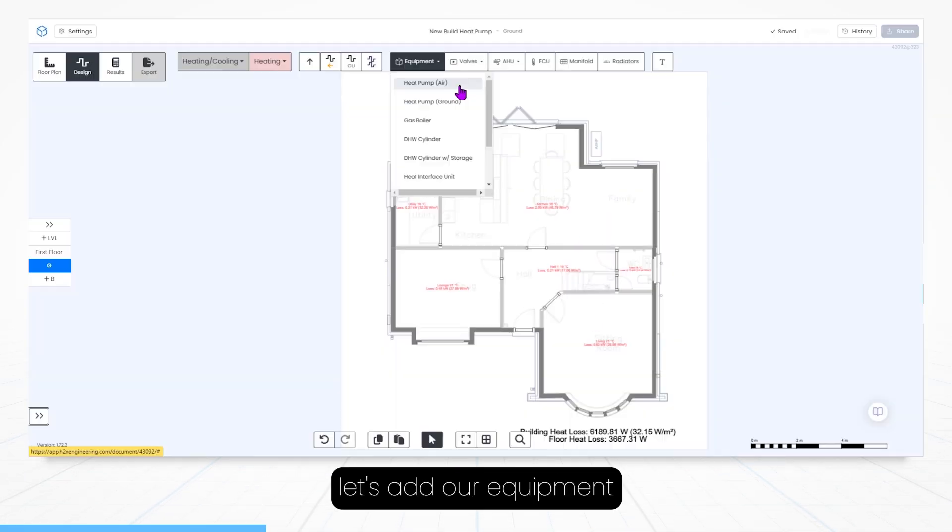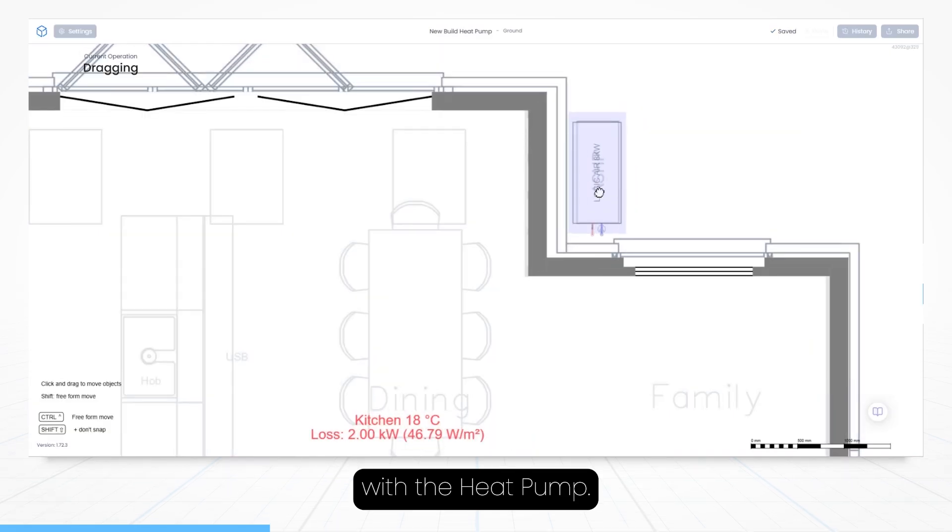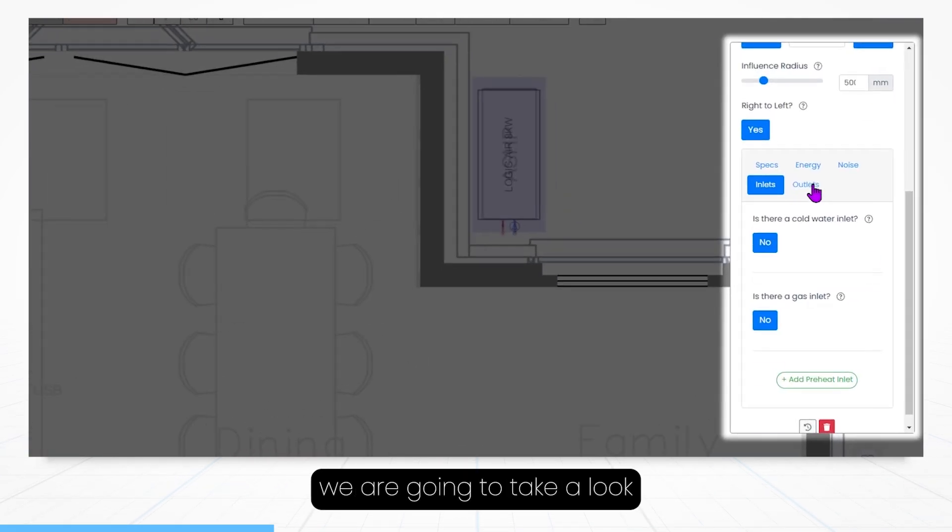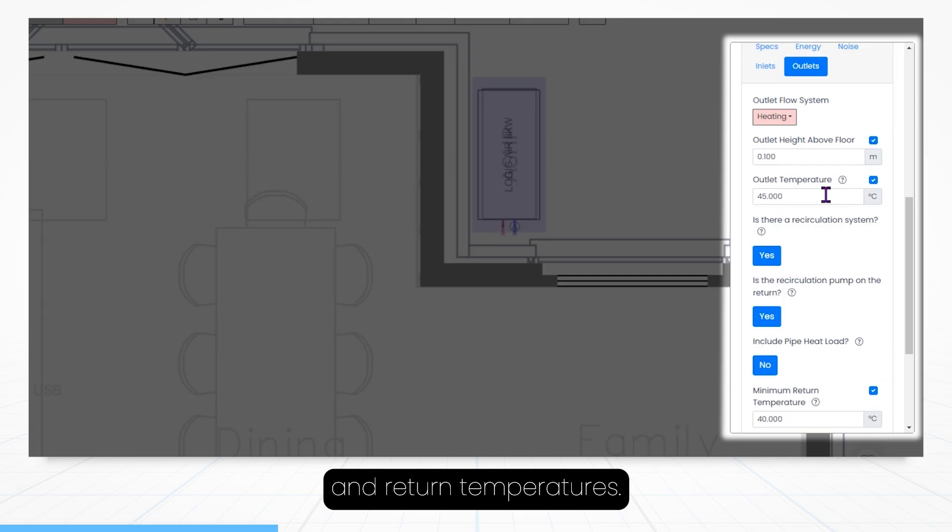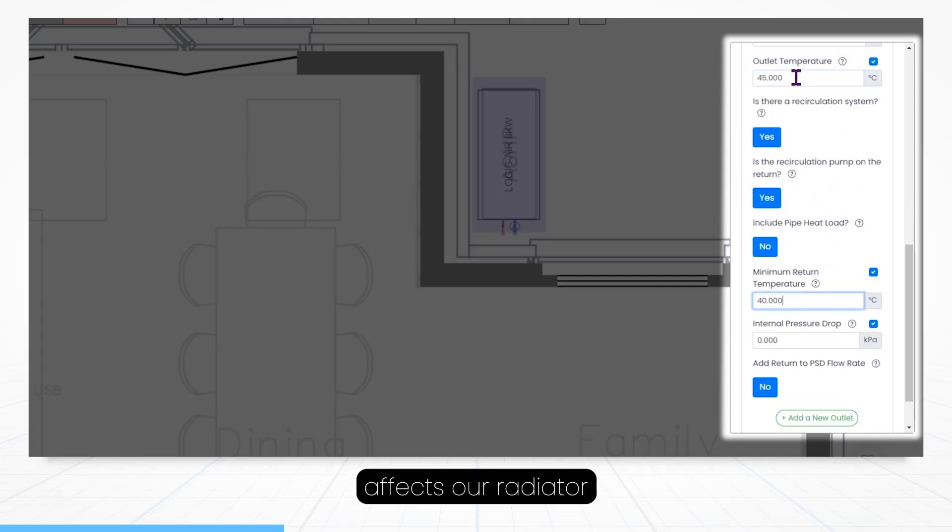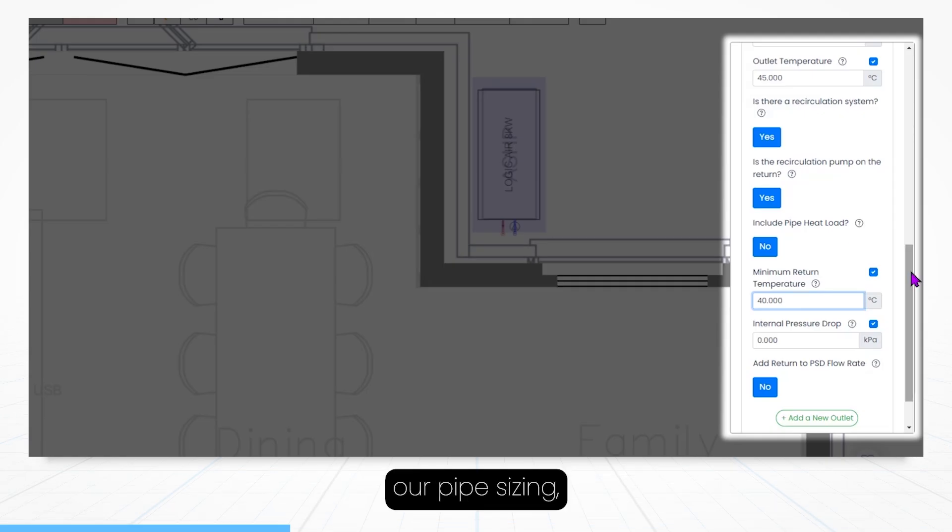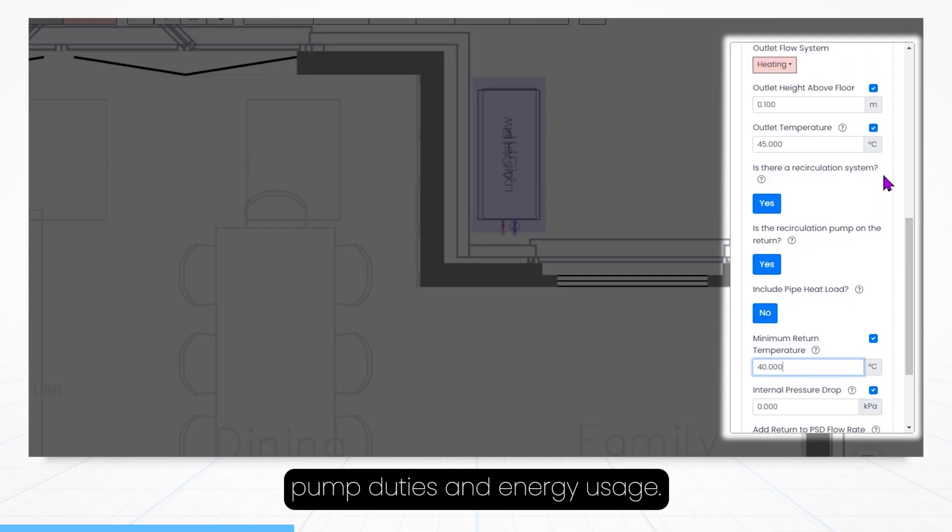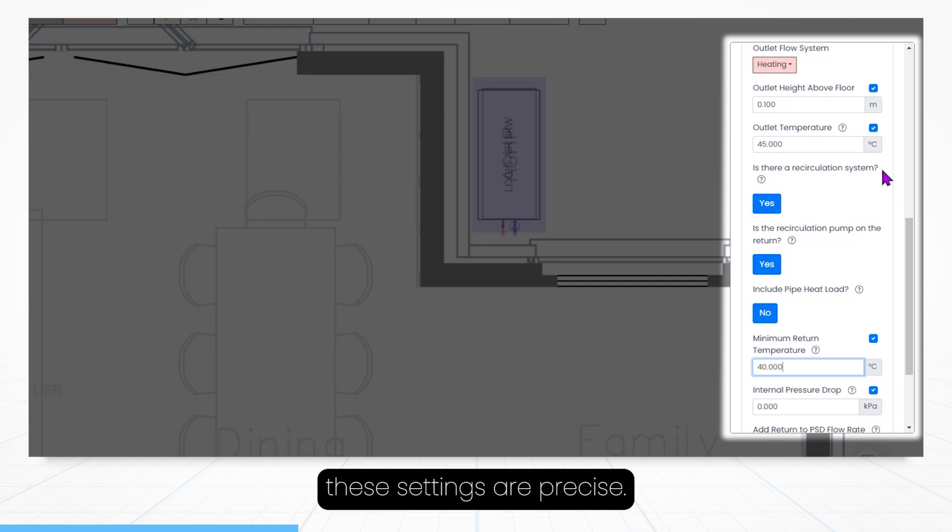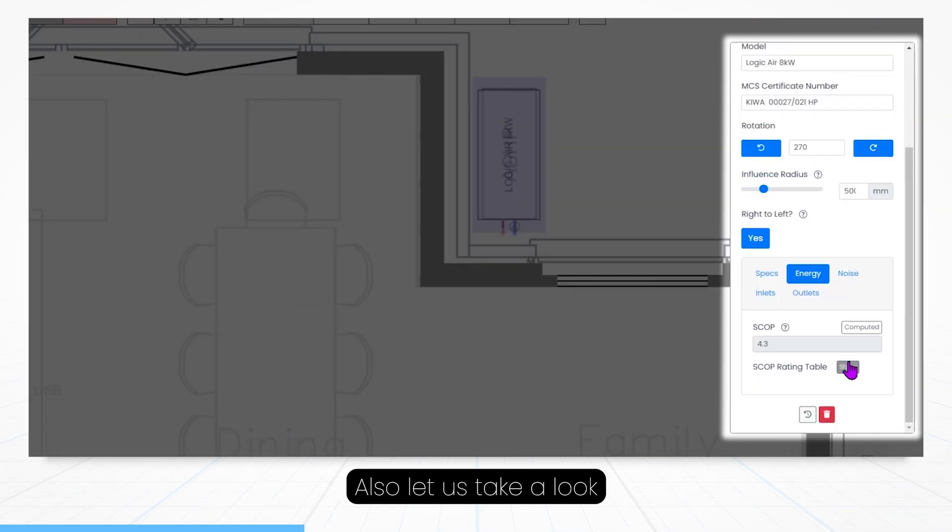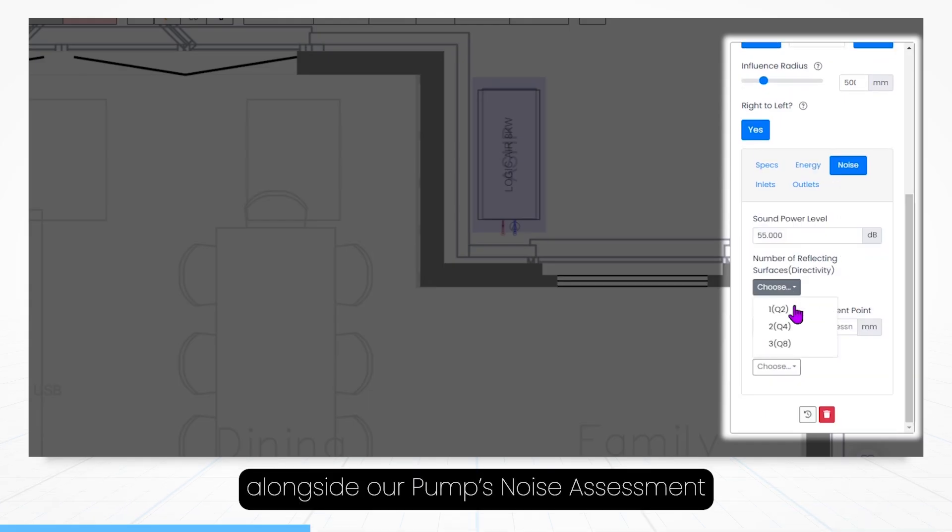And now to begin our heating design let's add our equipment, and we'll start with the heat pump. Now entering our heat pump settings we are going to take a look at our flow and return temperatures. This directly affects our radiator and underfloor heating outputs, our pipe sizing, pump duties and energy usage, so it's important that we make sure these settings are precise. The heat pump settings also let us take a look at our SCOP rating alongside our pump's noise assessment.